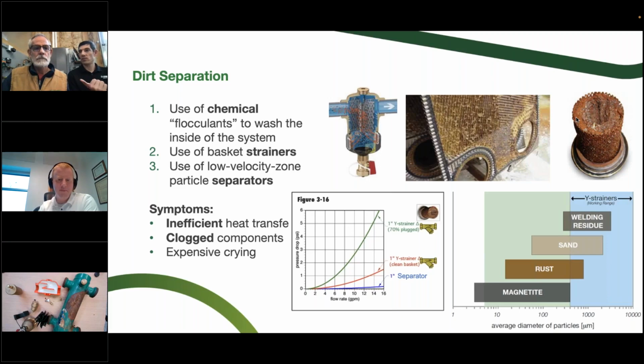So basket strainers, you've described them before as point of use protection. Maybe you still have a basket strainer by a fan coil or by a balancing valve somewhere out in a big commercial building, but the point of distribution is a great spot for a dirt separator, because that's where we're going to protect our most expensive components, and that's where we have a combined flow rate for the entire system. So maybe a 2-inch flanged is a good fit there, where you wouldn't put 1-inch dirt separators in 20 different fan coils in a building, as one example.